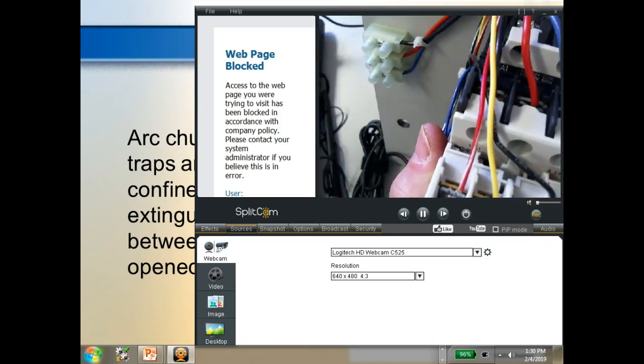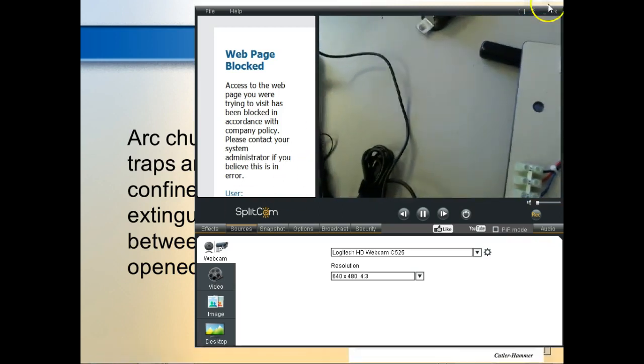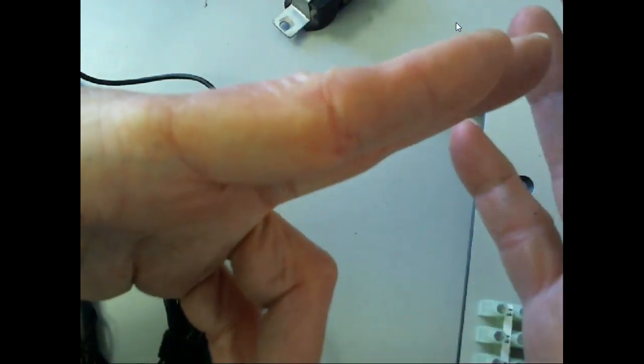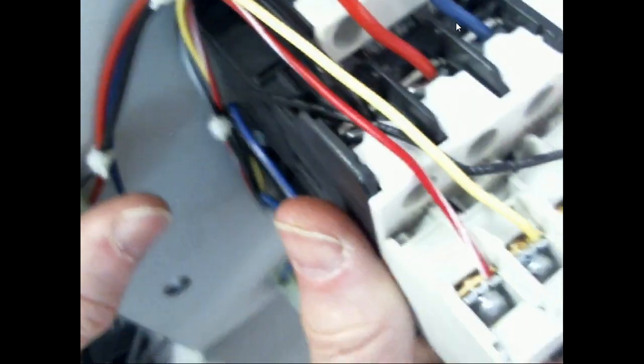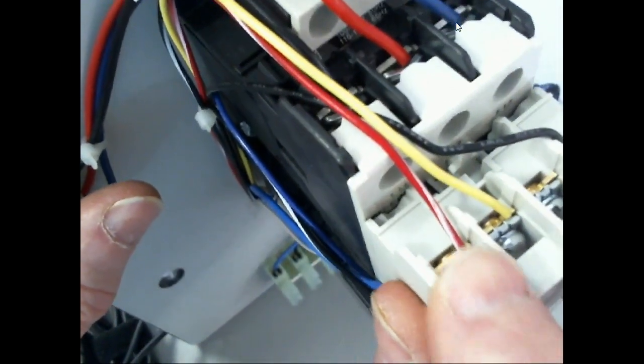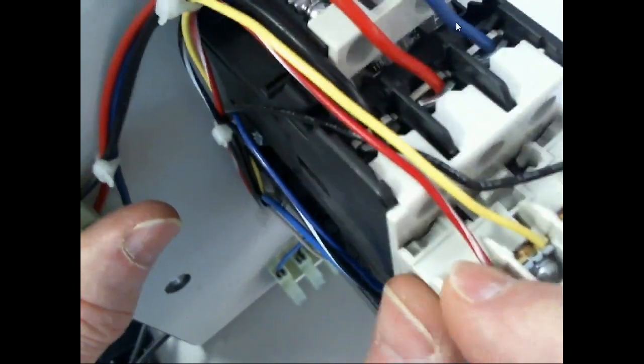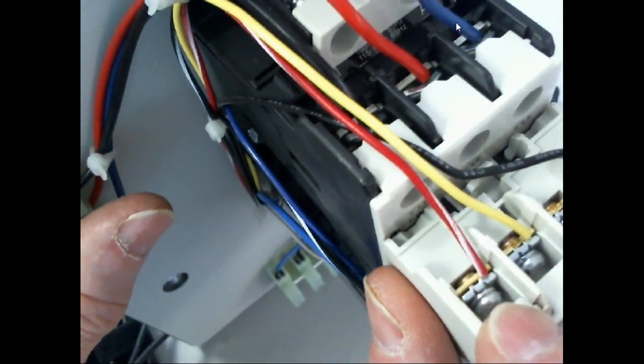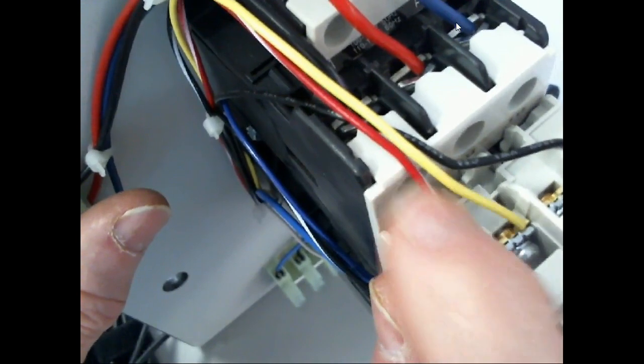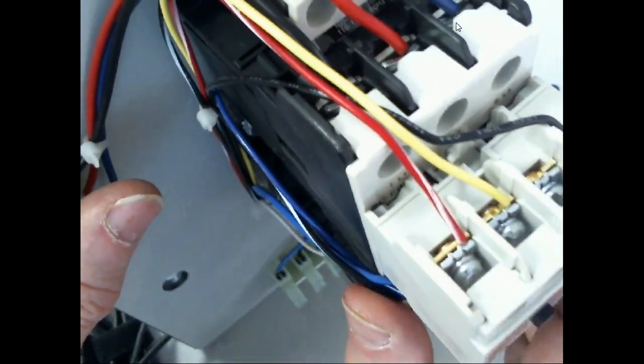The problem we have with stranded wire is that stranded wire does what we call birdcage, which means when you put it under a screw, it wants to spread out. And if a couple of wires come out from under there, then that means you messed up. So what they do now is they confine it. So when it birdcages, it has nowhere to go. Can y'all see what I'm talking about? So this terminal right here would be good for solid and for stranded wire. Can't go nowhere.